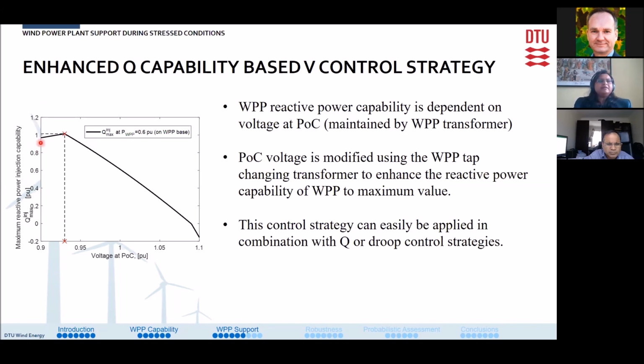We can see here that as the voltage increases, the reactive power capability increases, but after this point it starts decreasing with increase in voltage. Therefore, if we can find this value of maximum reactive power and the corresponding voltage at which it is obtained for a particular operating point and a particular active power production, then we can modify the wind power plant voltage, the point of connection voltage, using the wind power plant tap changing transformer and enhance the reactive power capability of the wind turbine.